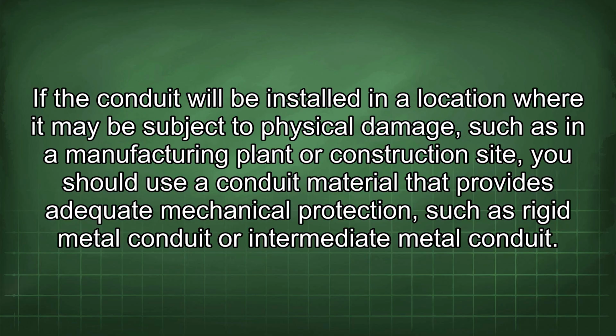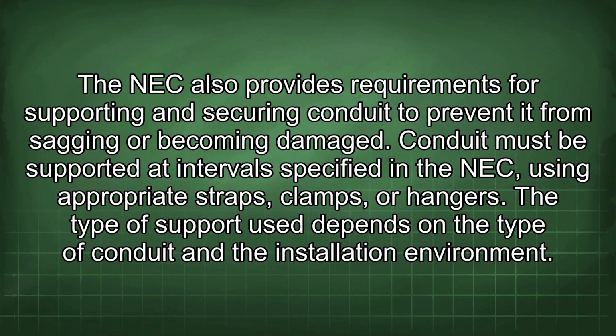If the conduit will be installed in a location where it may be subject to physical damage, such as in a manufacturing plant or construction site, you should use a conduit material that provides adequate mechanical protection, such as rigid metal conduit or intermediate metal conduit. The NEC also provides requirements for supporting and securing conduit to prevent it from sagging or becoming damaged. Conduit must be supported at intervals specified in the NEC using appropriate straps, clamps, or hangers. The type of support used depends on the type of conduit and the installation environment.